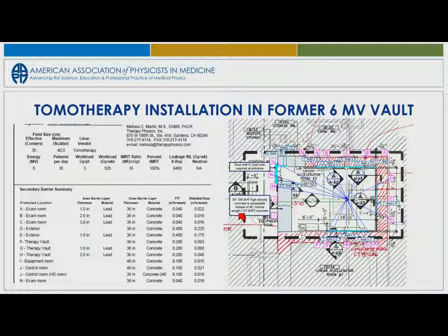We have had the privilege of designing the shielding for all of Cedars Sinai's retrofits. Do you know how long Cedars Sinai's been around? A long time. Those rooms are like patchwork quilts. They've got a little bit of lead here, a little bit of lead there, spaced out all over those ceilings. So when you do those, you wind up doing crazy things like this, needing a little bit of lead here, a little bit there, spaced out all the way around.